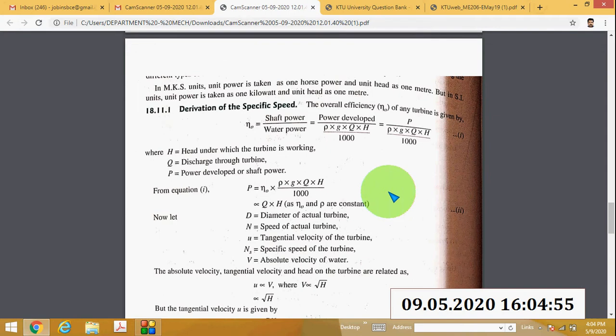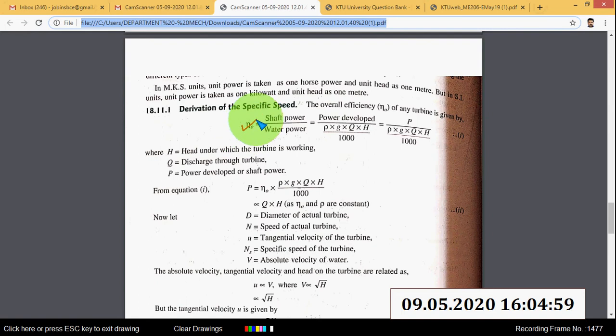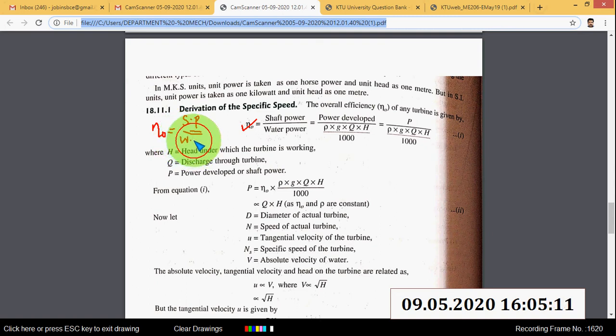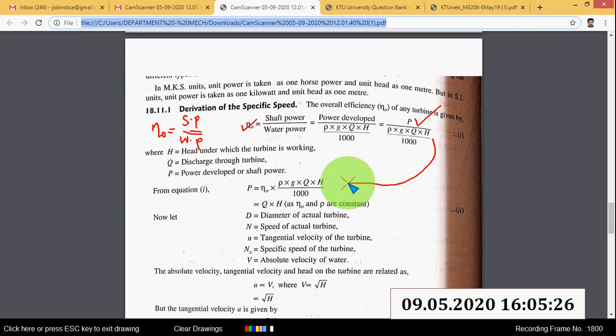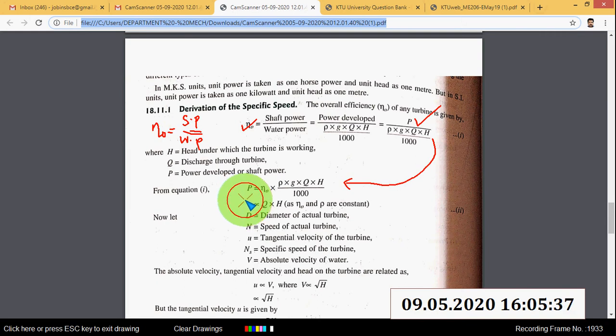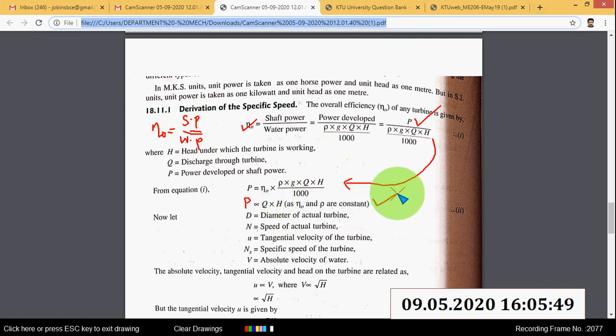First, write the overall efficiency equation. Overall efficiency is equal to shaft power (SP) divided by water power (WP). The equation of water power is ρgQH/1000. From this, P is equal to overall efficiency into ρgQH/1000. So P is proportional to Q into H, where other values are constant.